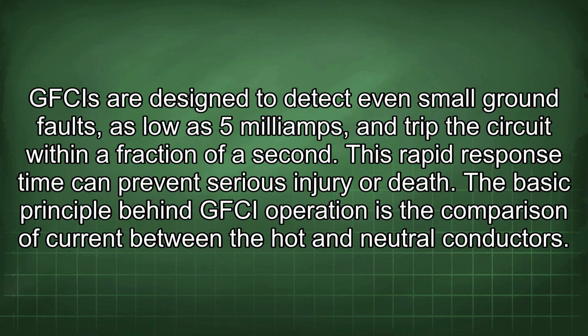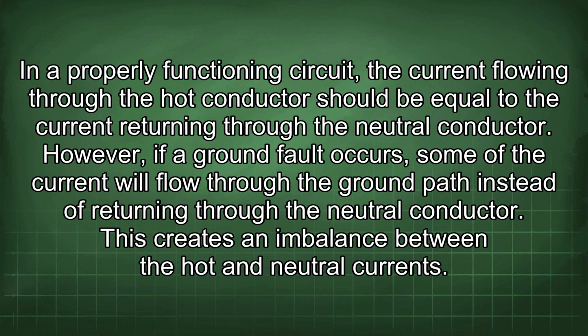The basic principle behind GFCI operation is the comparison of current between the hot and neutral conductors. In a properly functioning circuit, the current flowing through the hot conductor should be equal to the current returning through the neutral conductor. However, if a ground fault occurs, some of the current will flow through the ground path instead of returning through the neutral conductor. This creates an imbalance between the hot and neutral currents.